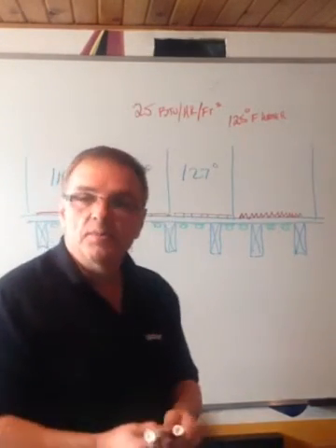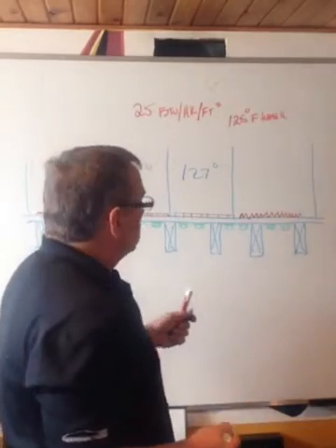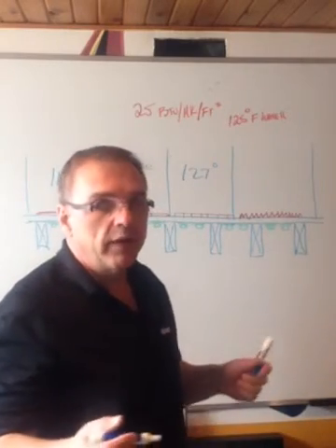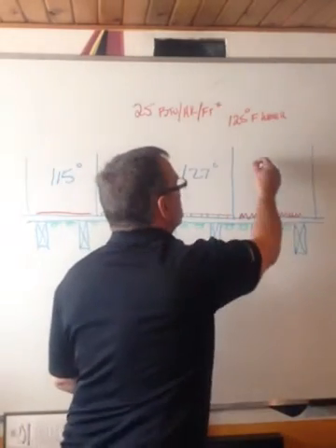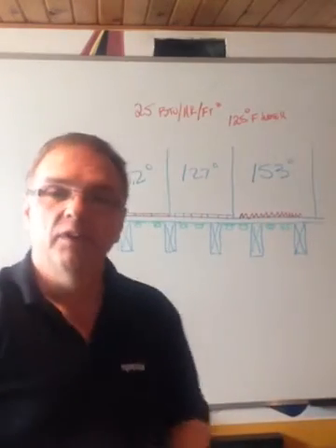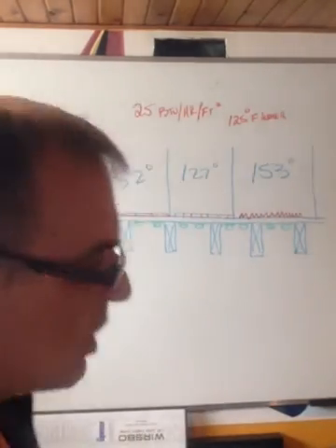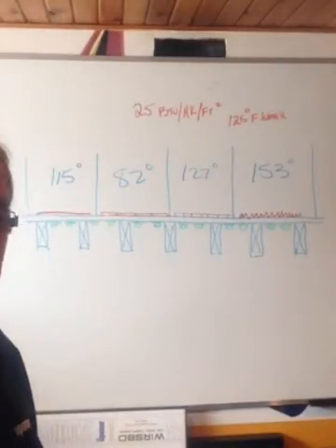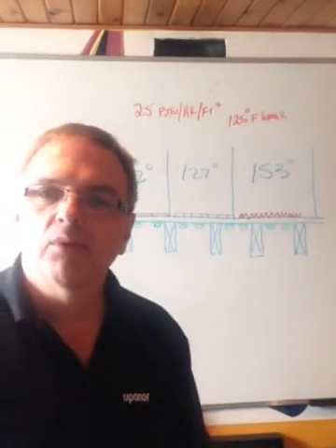And the last one, bedrooms. Maybe you want some plush carpet in there with underlay, and generally that's pretty thick. So we said 3/4 inch underlay, 5/8 carpet. Come up with an R value of about 2 on that, so the water temperature in this case is 153 degrees. So you can see the floor covering can dramatically change the water temperature required.